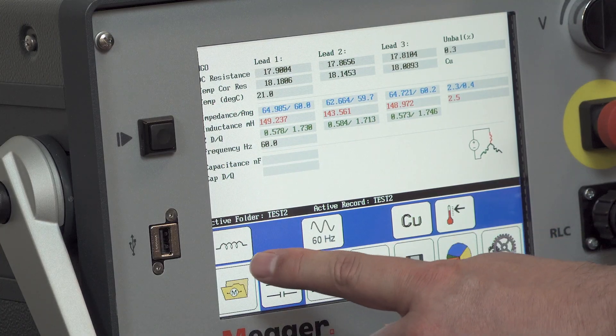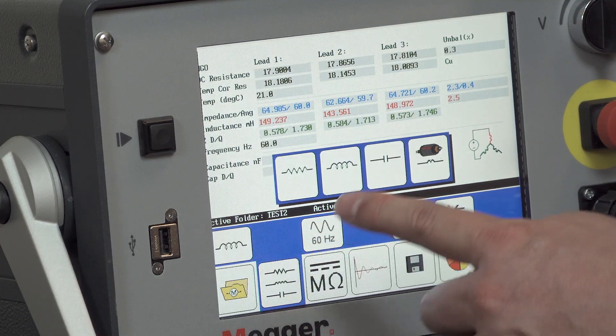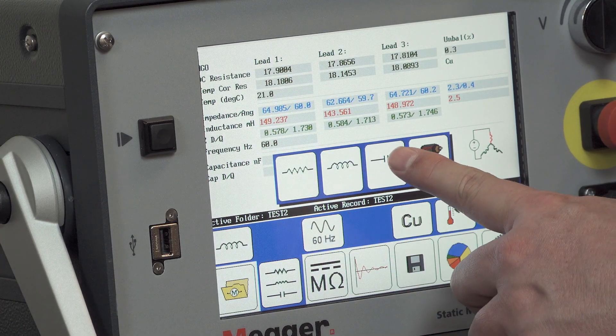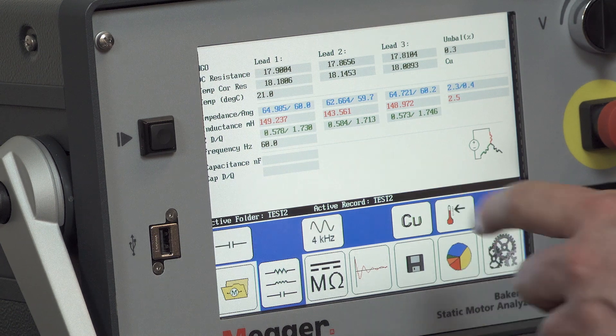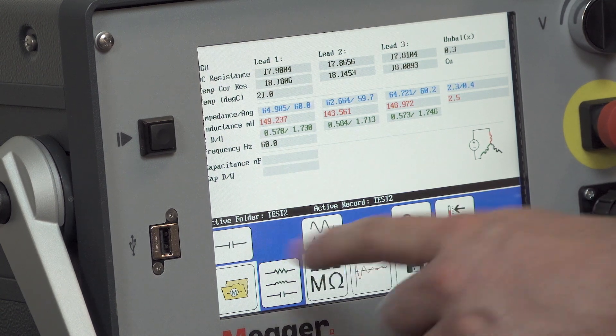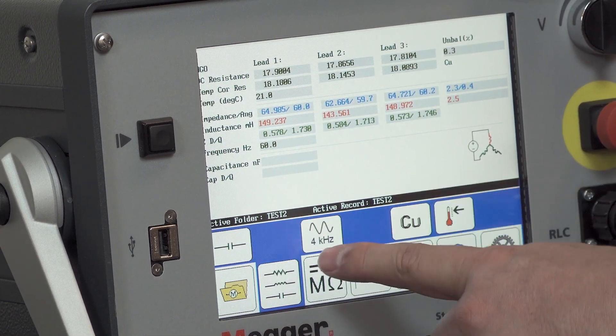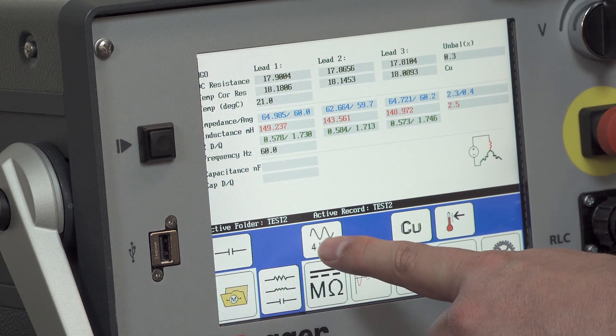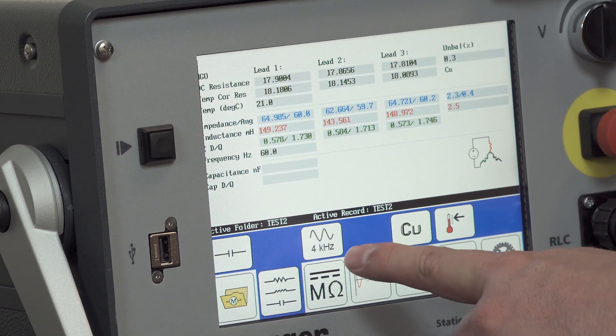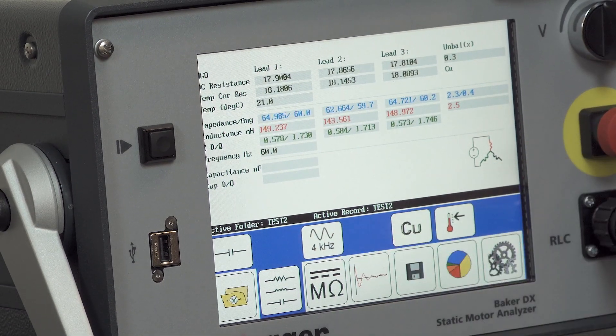Now to perform capacitance measurement, select the test mode and then select the capacitance icon. See it's selected there. Now capacitance measurement is always conducted at 4 kHz.